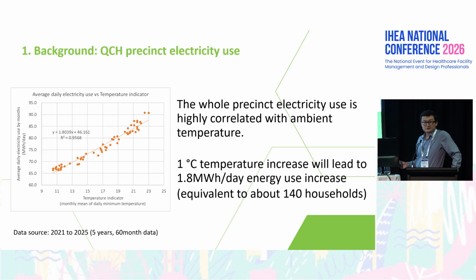I don't want to go too much into the math behind this chart, but in one sentence: the whole precinct's electricity use is highly correlated with ambient temperature, and a 1 degree Celsius temperature increase leads to 1.8 megawatt hours a day increase in electricity use. Our hospital uses about as much electricity as 5,000 households in southeast Queensland, and this 1 degree increase equates to about 140 households' worth of electricity use.